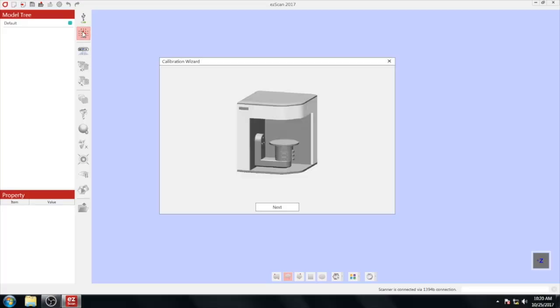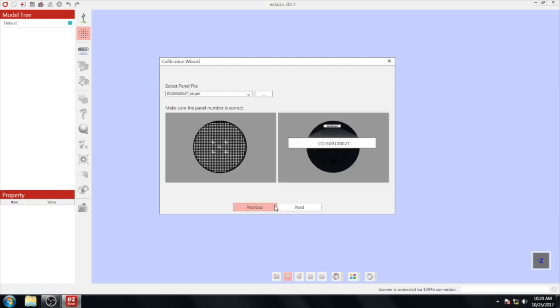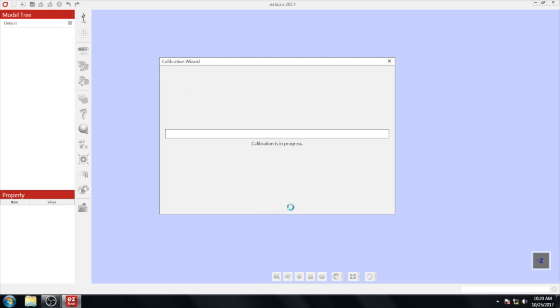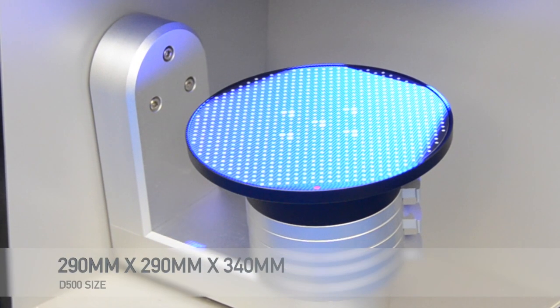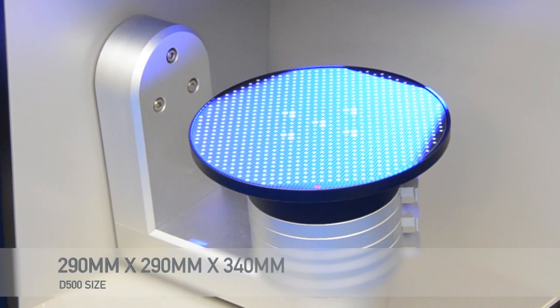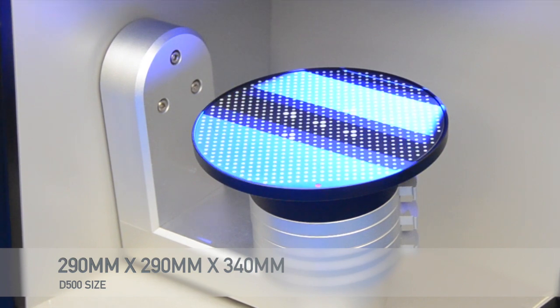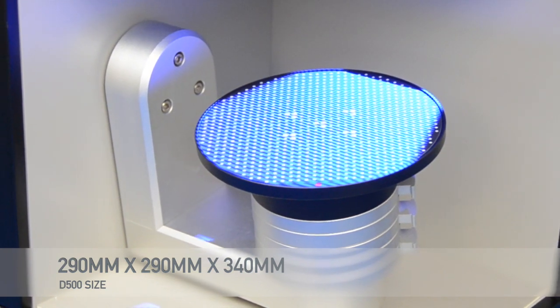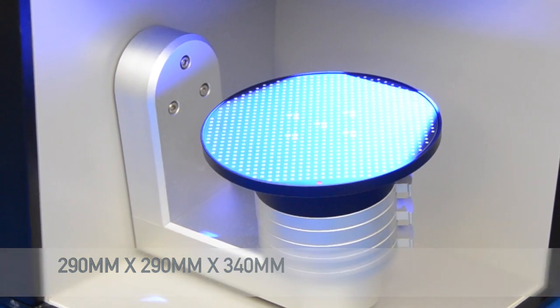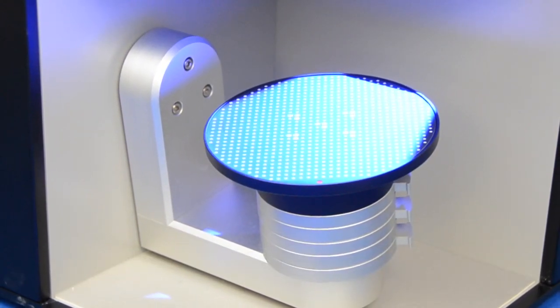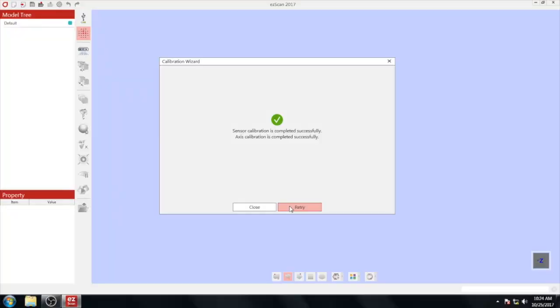Follow the on-screen instructions, making sure the on-screen panel number matches your calibration panel. Click next and the calibration will begin automatically. Calibration should take approximately 3 minutes. Once calibration has completed successfully, cover and remove the calibration plate. We recommend calibrating the scanner once a week.